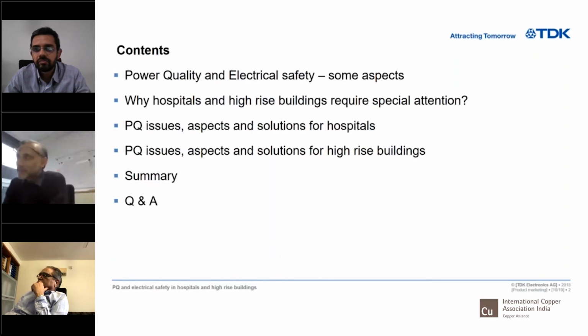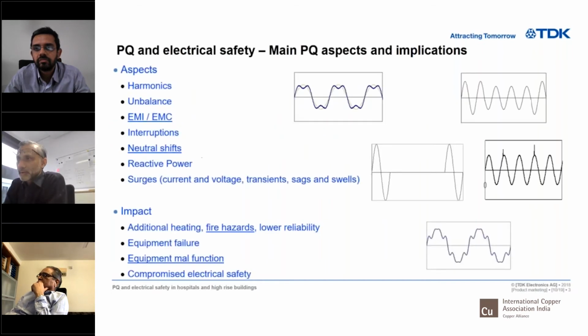Now we talk about electrical power safety and power quality. There are a lot of power quality parameters—I've listed a few—and these affect safety. We know power quality affects kVAh billing, energy, power factor incentives and penalties, and energy conservation. That's known, but parameters like harmonics, unbalance, electromagnetic interference, interruptions, neutral shift, reactive power and surges, apart from damaging equipment and the electricity bill, can actually affect safety.